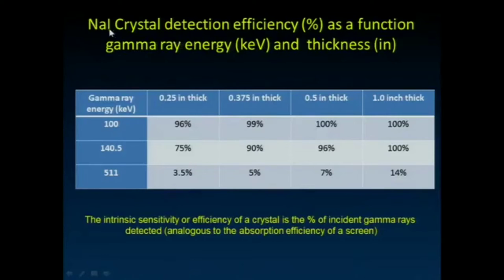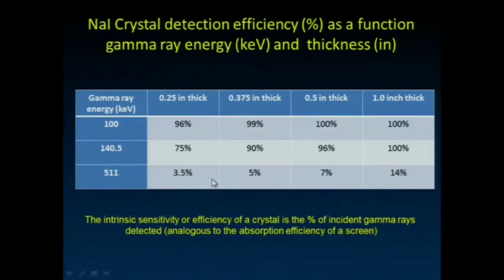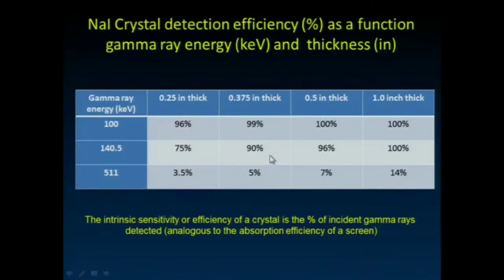Let's look at the sodium iodide crystal's efficiency for stopping gamma rays of particular energies. At 100 keV, 140 keV — this is technetium — and up to 511 keV as in PET, we compare quarter-inch, three-eighths-inch, and thicker crystals. For 140.5 keV, the three-eighths inch thickness stops about 90% of gamma rays from technetium-99m, which is very nice.